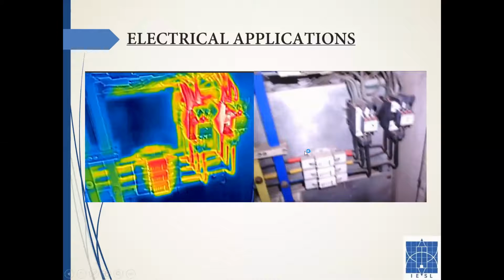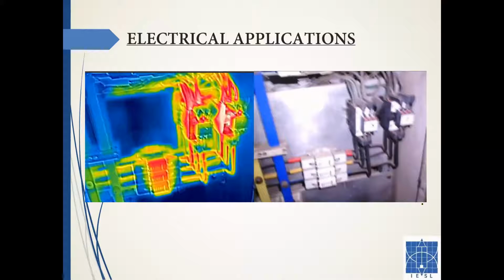What I was trying to say is that here we have an obvious faulty contactor. Please excuse the poor focus. In this contactor, you can see there is an obvious thermal signature right here. So this is a bad contact case. This is exactly where the contacts of the contactor are situated. You should see that there is obviously an internal problem.